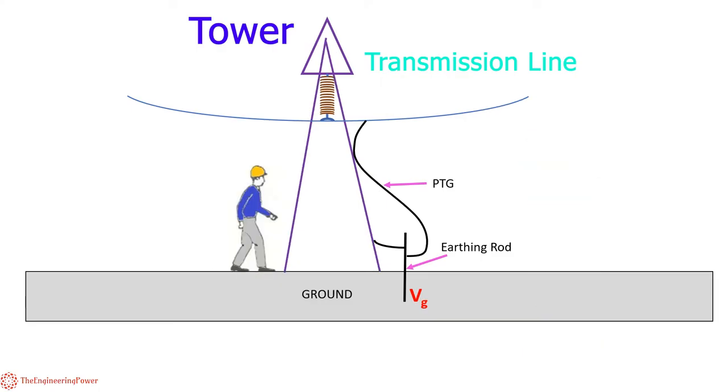Similarly, consider another person standing at point C who touches the tower during fault conditions. He will also suffer electric shock due to the potential difference between hand and feet of the person. As the hand of the person is touching the tower, which is at ground potential VG, whereas his feet are at point C, which are at a different potential VC. This potential experienced by the person standing on ground while touching the tower is called touch potential.